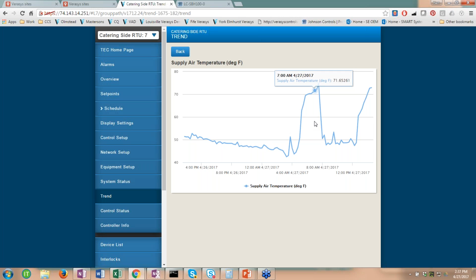And we have more information around control status. These are built-in sequences of operation and PID loops that are running in the system, so we also make sure we monitor those. If you're interested to see what the PID output of the cooling is, you would have to go into these sections. So I'm going to go back to the device list again, and I'm going to show you now the generic I/O. This generic I/O is really very simple, and all it's going to show us is 2 freeze temperature, and then the steam pressure that we have.